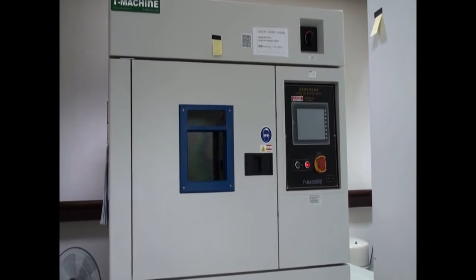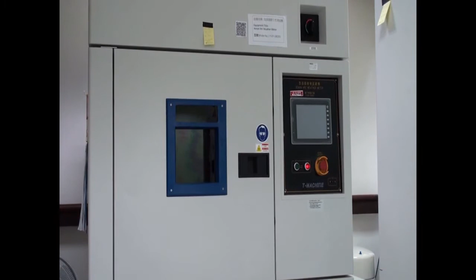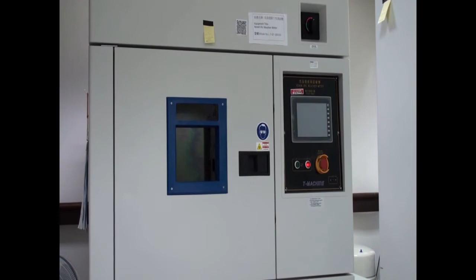The features of these machines are: it uses a xenon arc 6500 watt light source, and the wavelength range that it covers is from 300 to 800 nanometer. It can go up to different irradiation intensities also, such as only at 340 nanometer, only at 420 nanometer, and it also covers the range from 300 to 400 nanometer as well as from 300 nanometer to 800 nanometer. The chamber temperature range can go up to 95 degrees C and the minimum is 10 degrees C. And the humidity range that it can maintain inside the chamber is 20% RH to 98% RH.